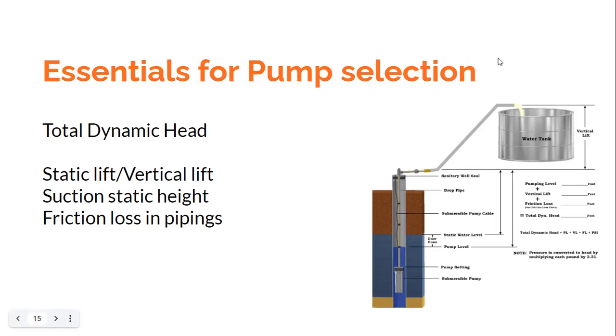In this diagram, there is also a pumping level — you can call it pumping level or suction static height. The tank above has a certain outlet. That outlet height — the height of the water outlet from the ground — is called the vertical lift or static lift. We can simply put a measuring tape up to the height where we need to lift the water to get the static lift. Both the static lift and the suction static height can be measured physically when you plan to install a pump.